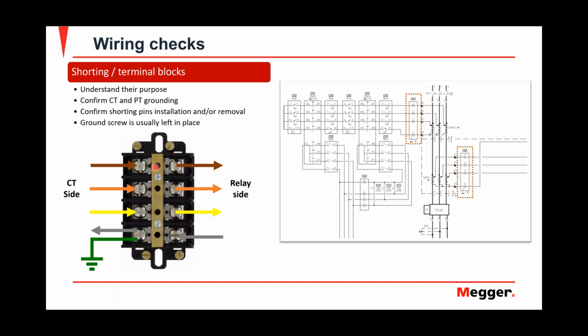I was at a site in New York City, a very prominent newspaper. The whole transformer went on fire. And this is how important it is, because this is real life what happened. The whole transformer blew up, went on fire. The relays didn't do anything. All the settings were correct, blah, blah, blah. It took us half an hour to realize that the shorting pins on all the relays at this site were left on from commissioning. So the guys always saw a voltage because you don't use shorting pins for the voltages.